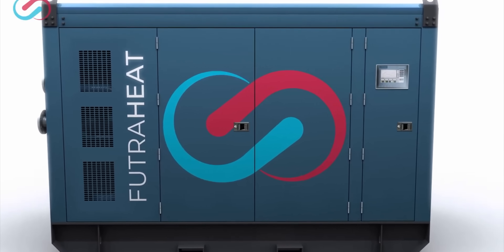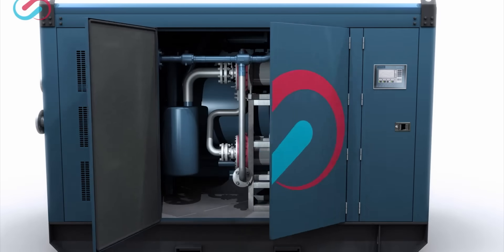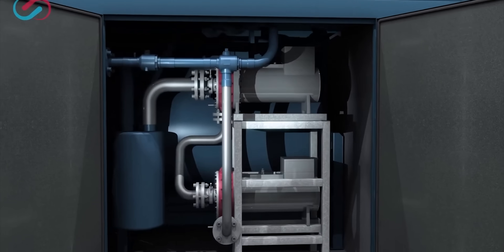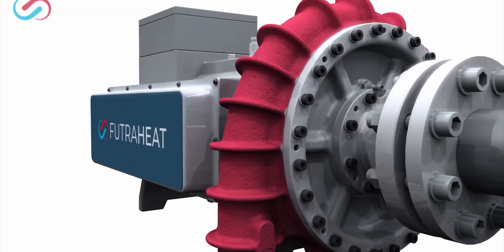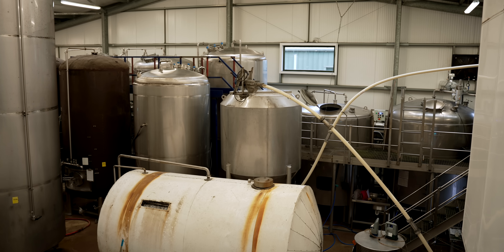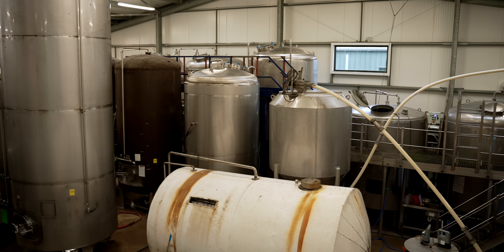You typically start with temperatures just below 100 degrees — 80 or 90 degrees — and take that back up in the form of steam to drive the process, closing that energy loop. Futraheat is one of a number of companies looking to do this, but what makes them different is that at the heart of their heat pump is a compressor called TurboClaw, which is unique to them. It's a turbo compressor that works at the size that most of industry needs — turbo compressors have existed for 100 years but they work best when compressing an awful lot of gas, which isn't what's needed here at one megawatt and sub-megawatt scale.